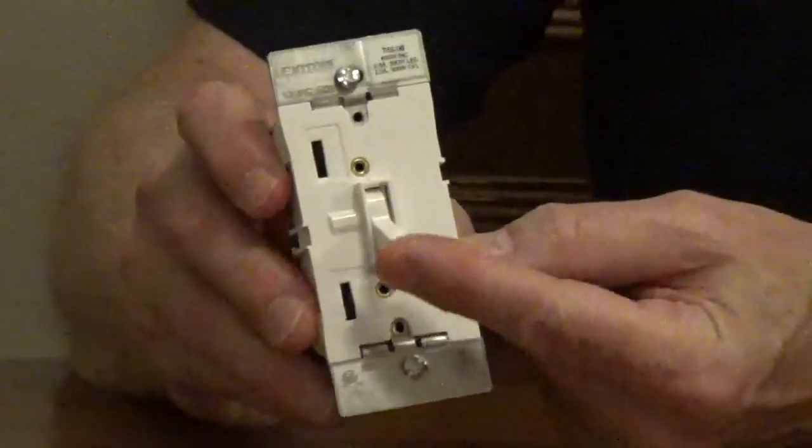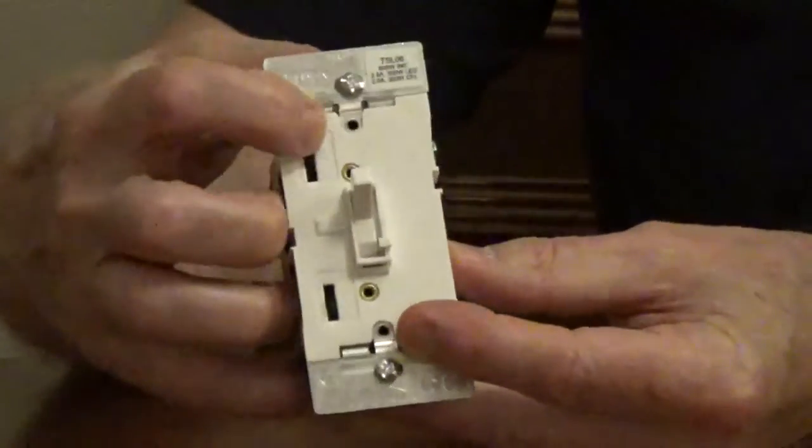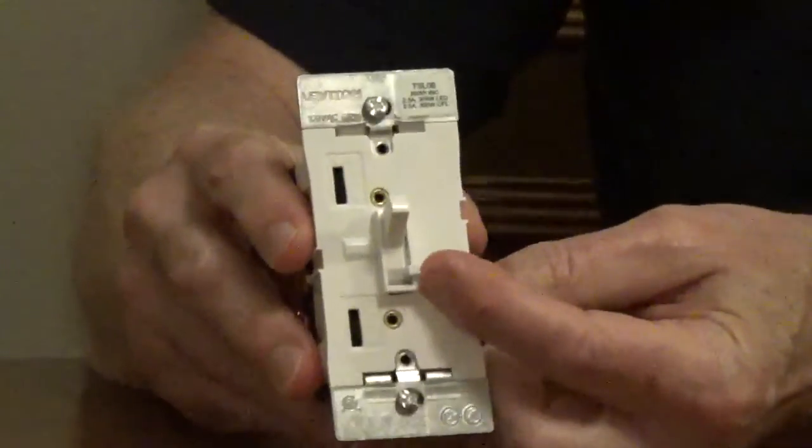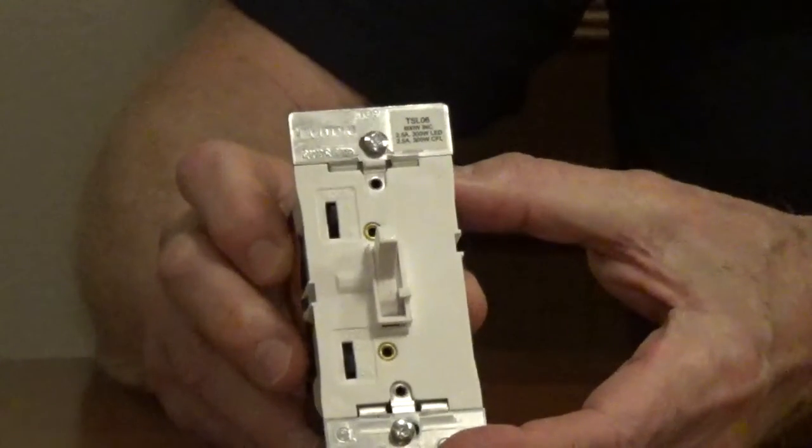Now you're going to turn it on, flip this to B, slowly move up the slide until there's no flickering, and flip it back to A, and now you've locked in the minimum load level.